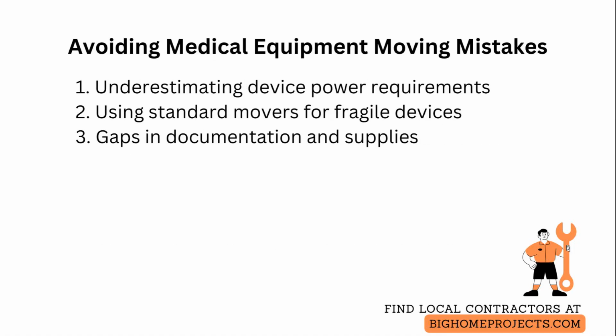Common mistakes are underestimating power requirements, which leads to device failure. So calculate continuous and peak loads and have a certified electrician confirm outlet capability or install a dedicated line. Another frequent issue is assuming fragile devices will tolerate standard movers, so avoid that by scheduling vendor or specialized medical equipment movers who understand calibration needs, and by labeling crates with device details and orientation.